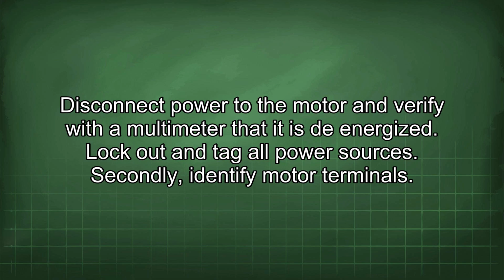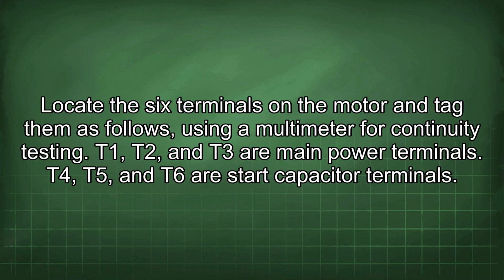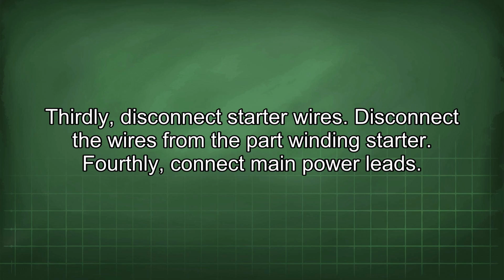Secondly, identify motor terminals. Locate the 6 terminals on the motor and tag them as follows, using a multimeter for continuity testing. T1, T2, and T3 are main power terminals. T4, T5, and T6 are start capacitor terminals. Thirdly, disconnect starter wires. Disconnect the wires from the part winding starter.